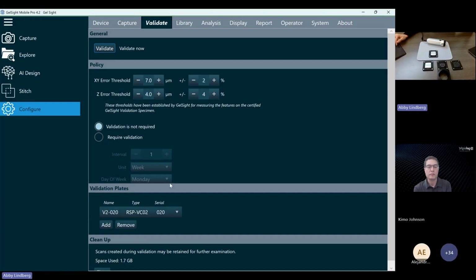The other thing we have on this page here is the validation plate listing. As mentioned, this plate has the certified depths and distances between those features. All of those come in an XML file to upload into your software. So when we take the scans of this plate, we're checking our measurements against those values from the certificate that's uploaded into that XML file.